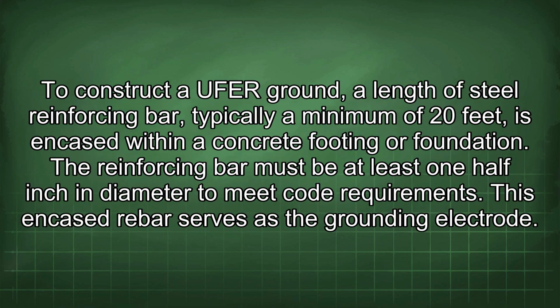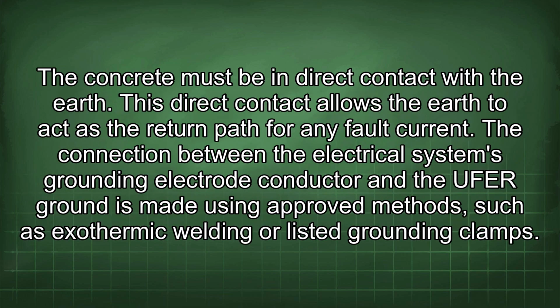To construct the UFER ground, a length of steel reinforcing bar, typically a minimum of 20 feet, is encased within a concrete footing or foundation. The reinforcing bar must be at least 1/2 inch in diameter to meet code requirements. This encased rebar serves as the grounding electrode. The concrete must be in direct contact with the earth. This direct contact allows the earth to act as the return path for any fault current.